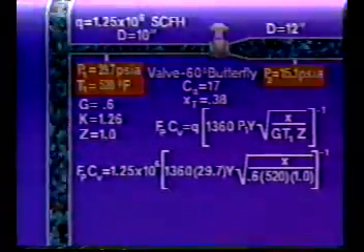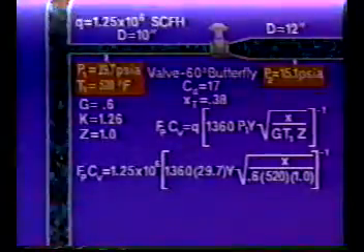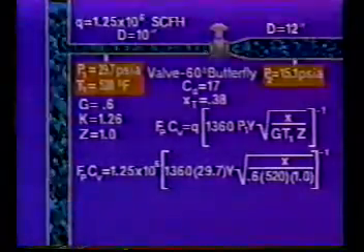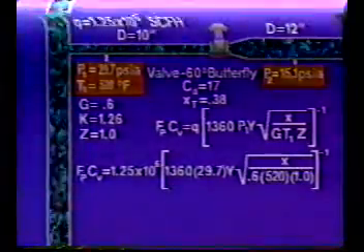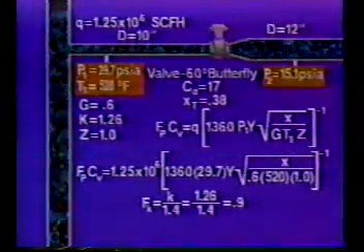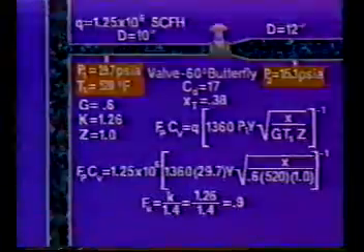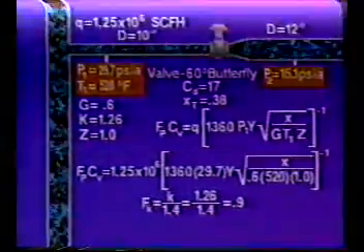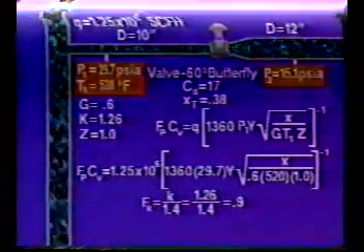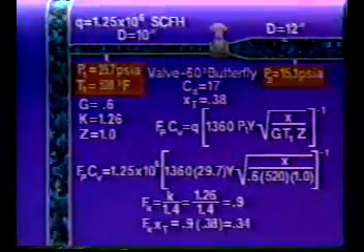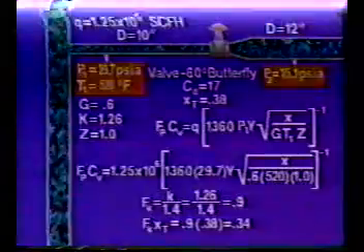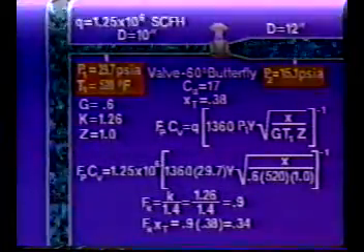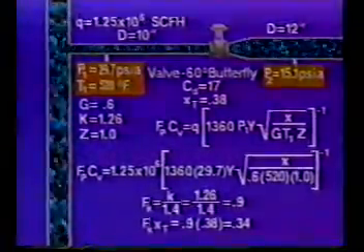You may also recall that the value of X sub T was determined experimentally. When fluids other than air are used, X sub T must be modified by F sub K, the ratio of specific heats factor. Now, for natural gas, F sub K is equal to 0.9, so the value of X to be used is the product of F sub K times X sub T, or 0.34.